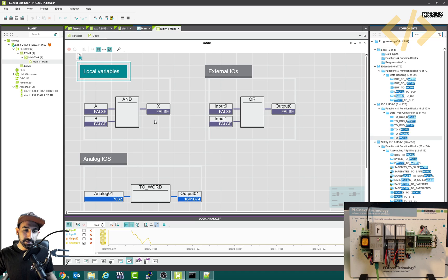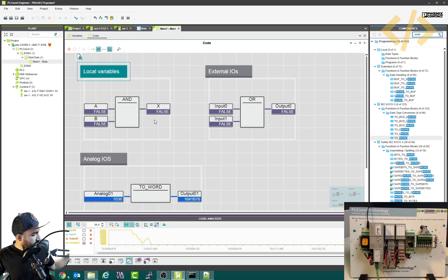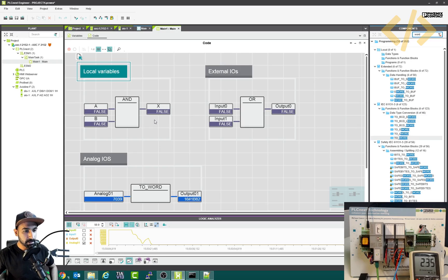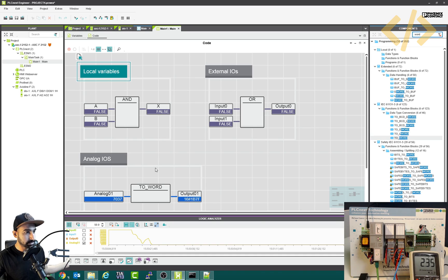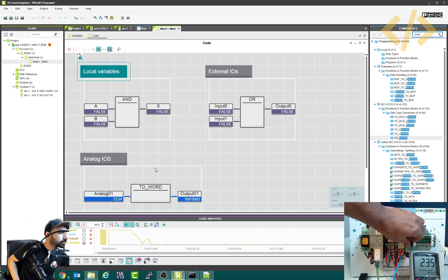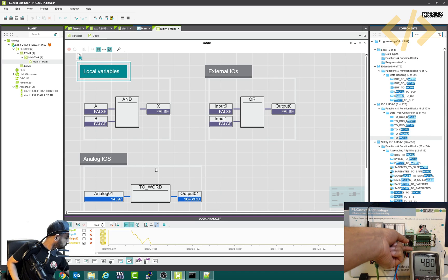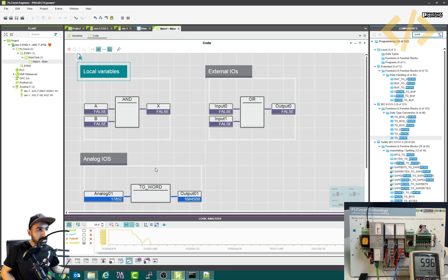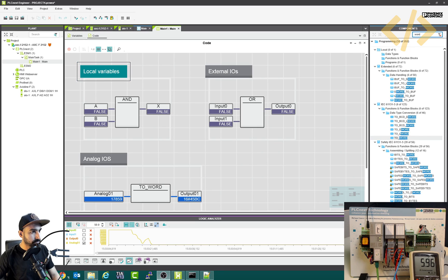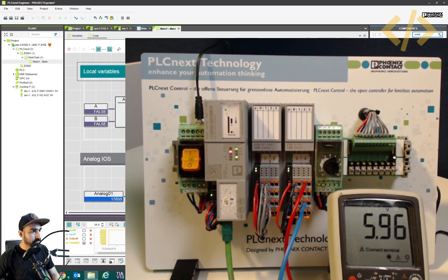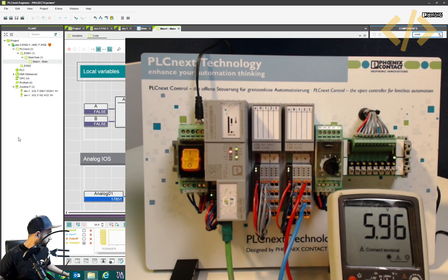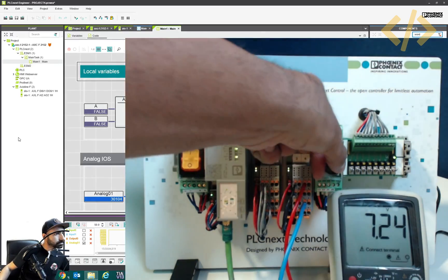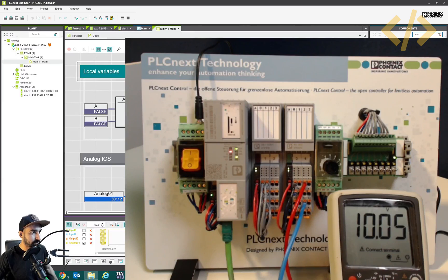To ensure the values are correctly linked to my analog input, I'll show you with a multimeter. My analog output is now connected to a multimeter, so when I rotate the knob changing the analog input, I can see my output is also changing. My knob is at 6 volts and you can see I have output 6 volts as well. When I move completely to 10 volts, I can see 10.05 on the multimeter.